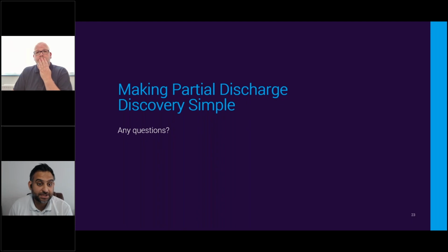It is. It is. So you can use Ultratev Plus 2 outdoors and on outdoor switchgear as well. Again, the issue with the inverter noise does come in, but there are some features on the instrument that allow you to differentiate between noise and genuine partial discharge activity.